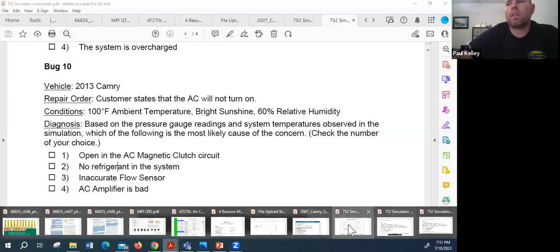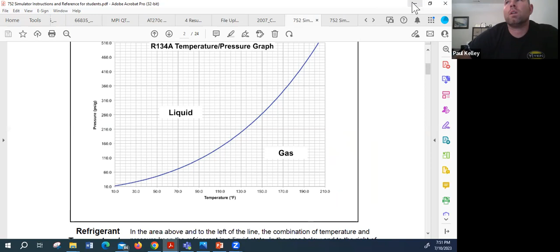So if we were to look at this one, it's an A, it was 100... 100 PSI? I mean, 100 degrees. Yeah, so if it's 100 outside and we look at that, 100 outside would be about like 140, 130 PSI. Well, I think that's kind of what we have. Yeah, 120, right? So we've got refrigerant in there. It's not empty, it may be slightly low, but maybe not. All right, so I think we can eliminate that.